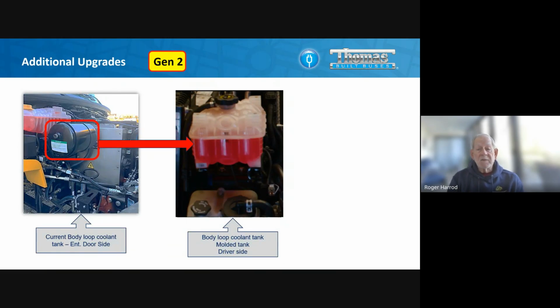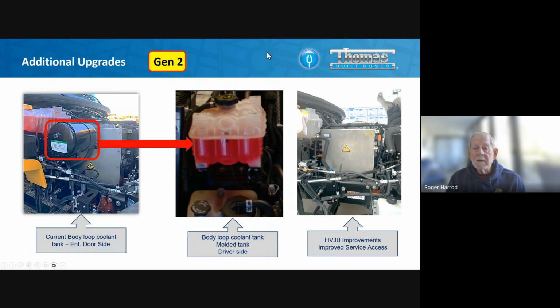Some other really nice changes as far as accessibility. The pink tank in the upper left-hand corner is for the cooling system for the batteries. The black tank is the expansion tank used for the body heat system, the interior of the bus. It was very inconveniently located right in front of the high voltage junction box, which is where technicians working on the high voltage system need access. We literally had to remove half the cooling system from the front of the unit to get into that box. This has been relocated to the other side of that front compartment. For reference, right below that red tank, you see the power steering reservoir. The real benefit is it opens up the whole side of the electronics controls, giving better access to the high voltage system as necessary.